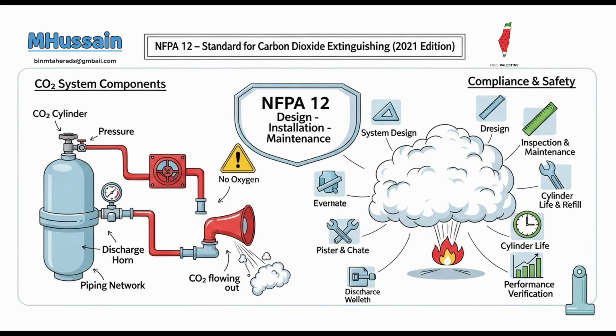How do you know the system is working or if there's a problem? Finally, supervision is a core element for reliability. Automatic systems and lockout valves are typically supervised, meaning their operational status is constantly monitored. Monitored electronically. Usually, yes. Any interconnections critical for the system's control and life safety, such as wiring to alarms or shutdown devices, must also be supervised. If an open circuit, a ground fault condition, or a loss of integrity in pneumatic control lines occurs, anything that would impair full system operation, it must result in a distinct trouble signal at a central monitoring panel. Trouble signal if anything's wrong. This ensures that any fault is promptly identified and addressed, maintaining the system's constant readiness. Think of it like a car's dashboard warning lights, but for a fire suppression system where lives and critical assets are at stake. Critical warning system.